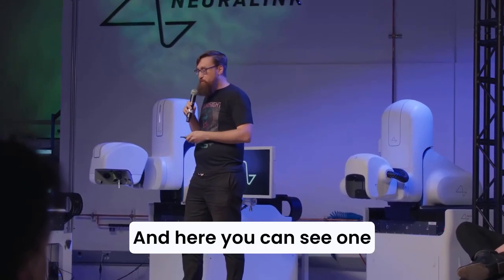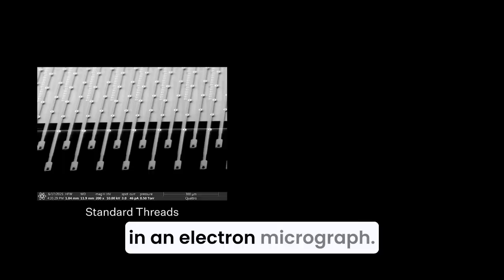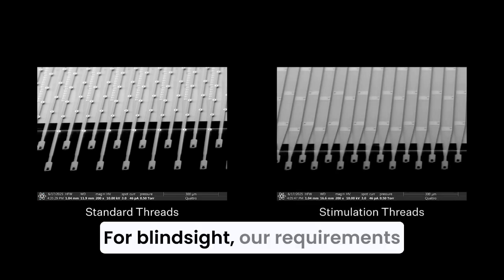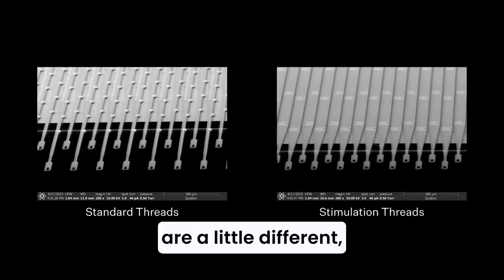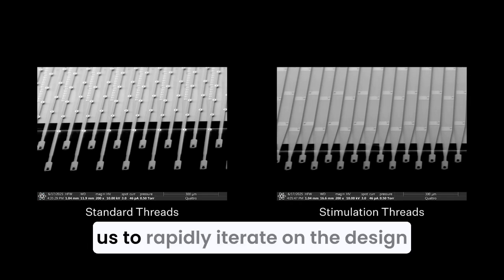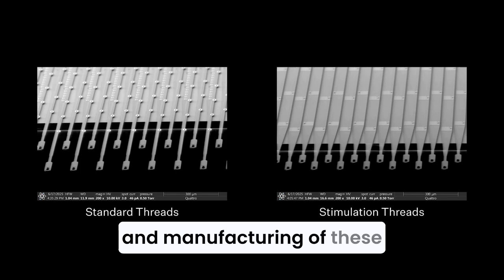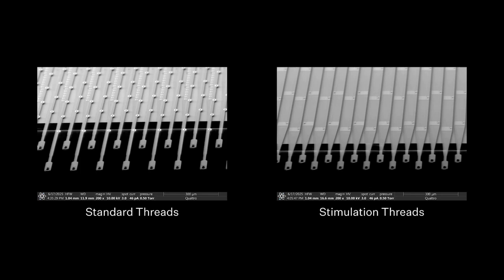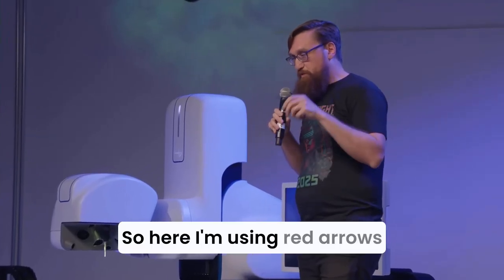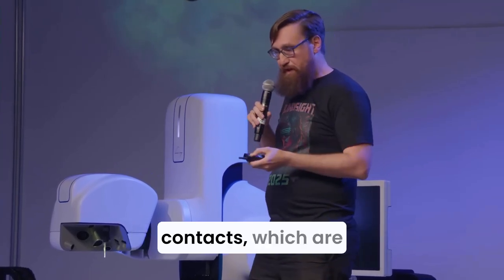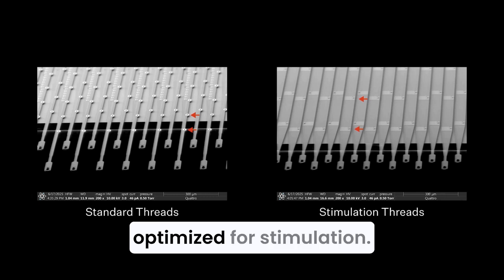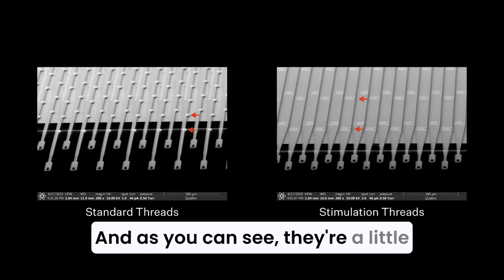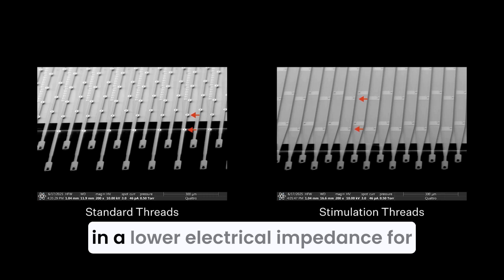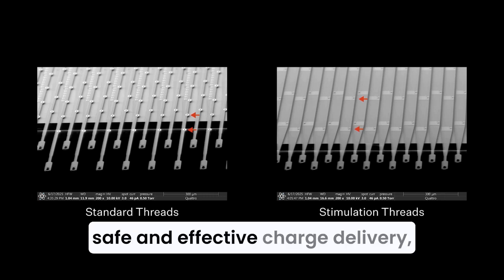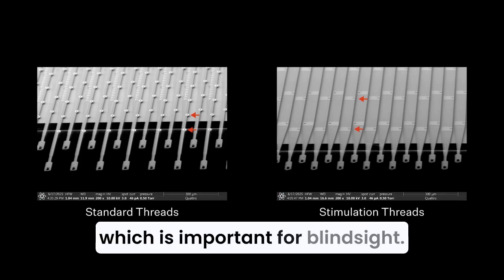And here you can see one of our standard threads designed for recording in an electron micrograph. For Blind Sight, our requirements are a little different, and our vertical integration allows us to rapidly iterate on the design and manufacturing of these threads for this new purpose. So here, I'm using red arrows to highlight the electrode contacts, which are optimized for stimulation. And as you can see, they're a little bit larger, which results in a lower electrical impedance for safe and effective charge delivery, which is important for Blind Sight.